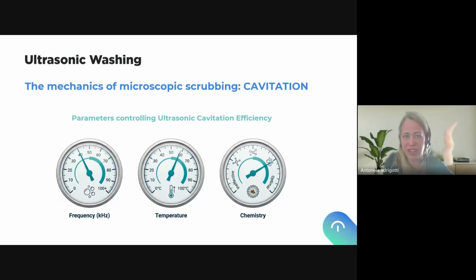for the regular washer machine, we also have frequency, which is a very important factor. And in here also, water quality, chemistry, temperature are very important because here there is a fine tuning that will define the cavitation energy, which is in the end the one that provokes the removal of the organic residues from the instruments. Frequency is very important because actually the machine needs to work in the ultrasonic range. And in this ultrasonic range, most of the ultrasonic washers work between 35 to 45 kilohertz.